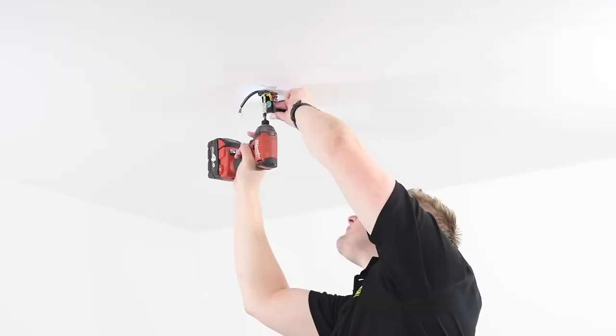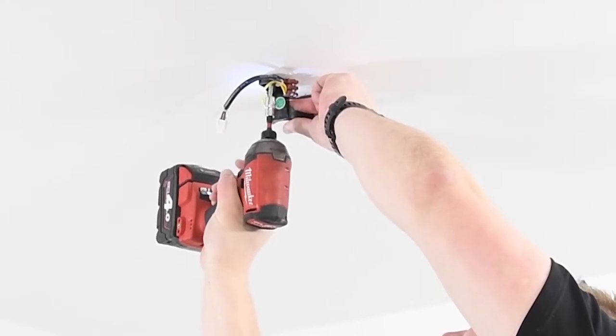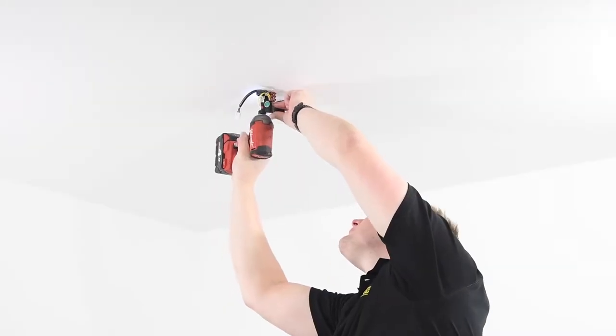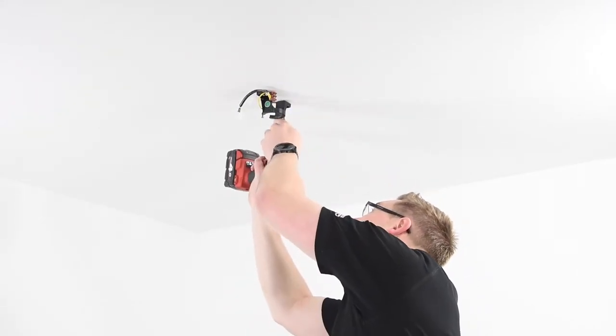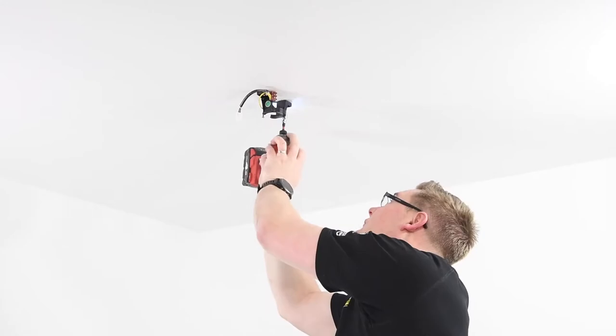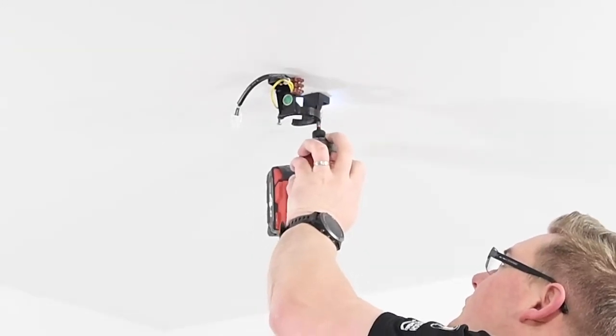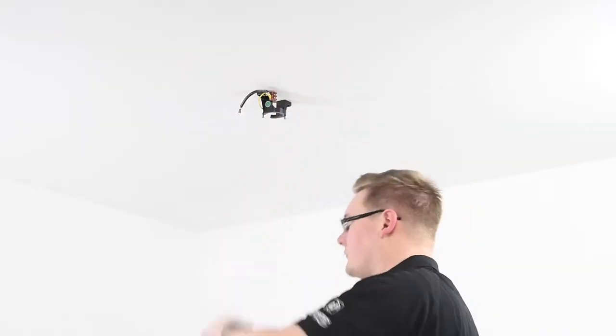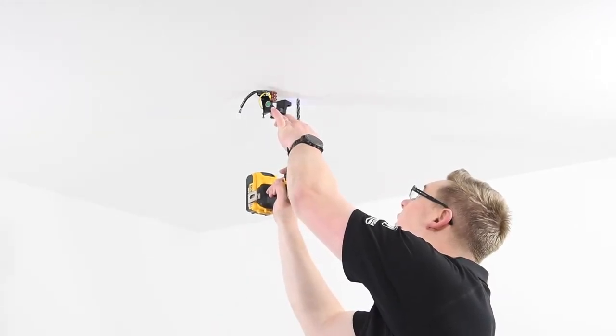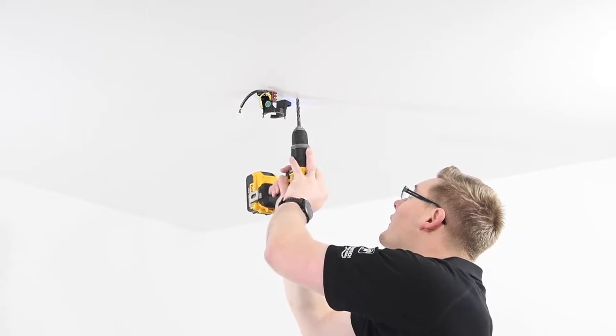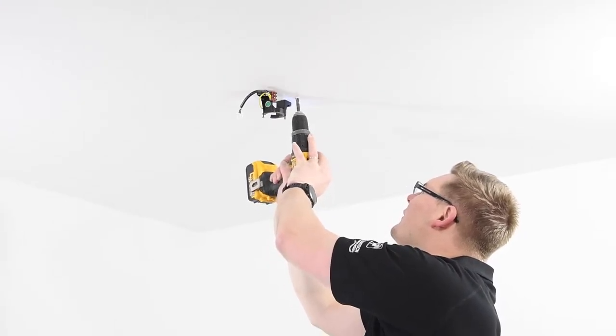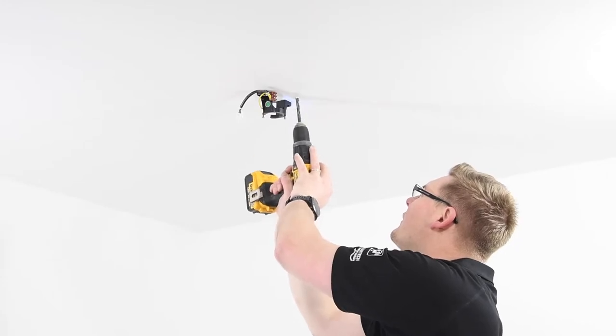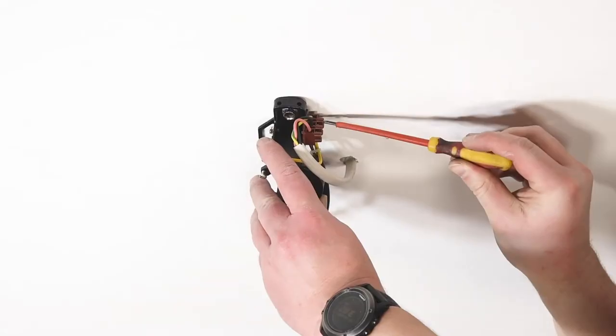Once you have selected a suitable location to install the fan, secure the mounting bracket to the ceiling joist using the supplied timber screws. If you are using a support made from material other than timber, ensure the correct fasteners are used to secure the mounting bracket. Drill a hole in the plaster just large enough to fit the mains wiring through that will be hidden by the fan's cover plate. Feed the mains wiring through, ensuring that it can reach the terminal strip on the mounting bracket comfortably.